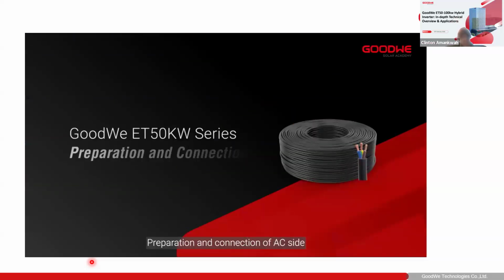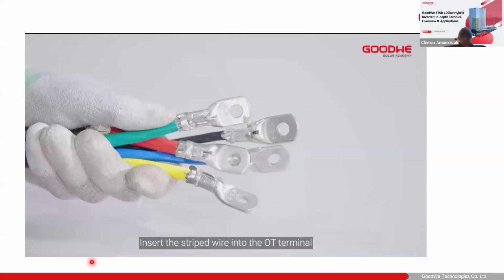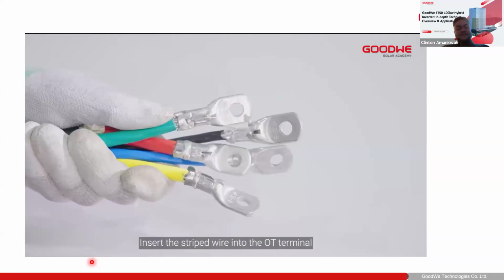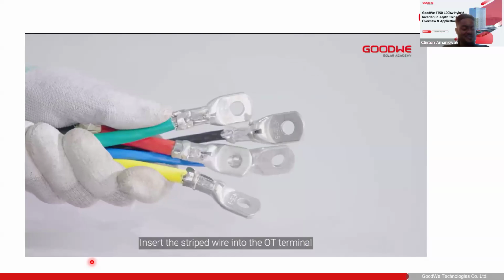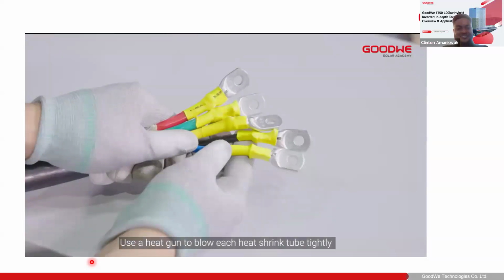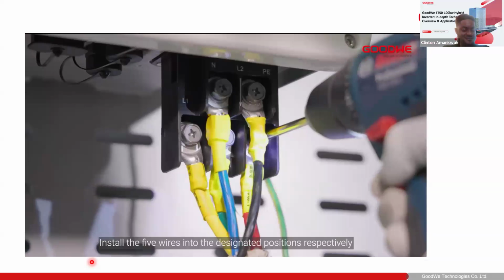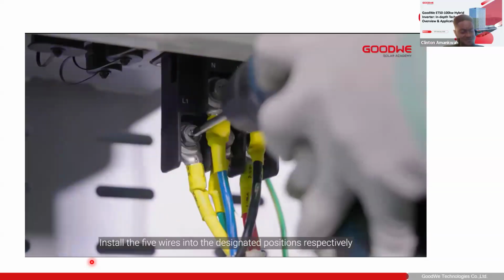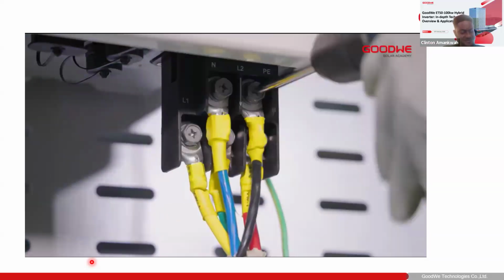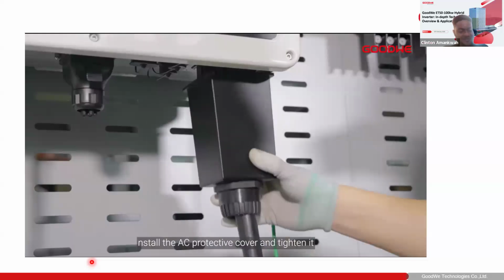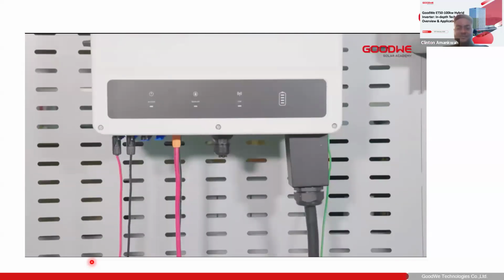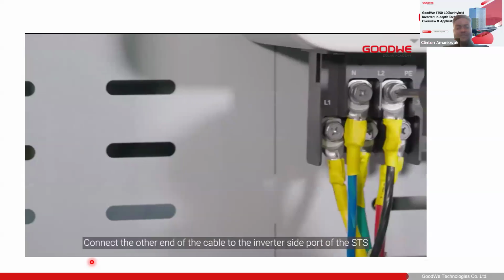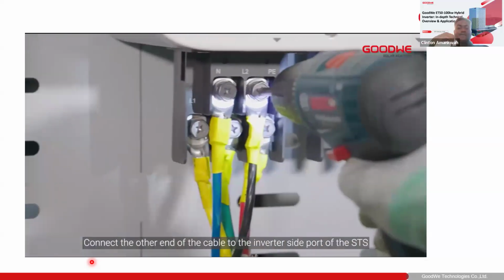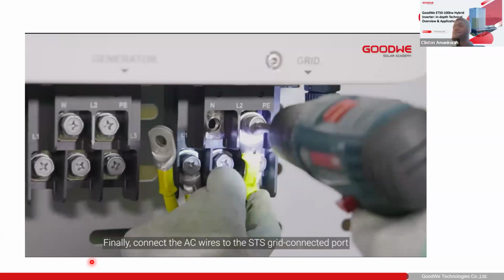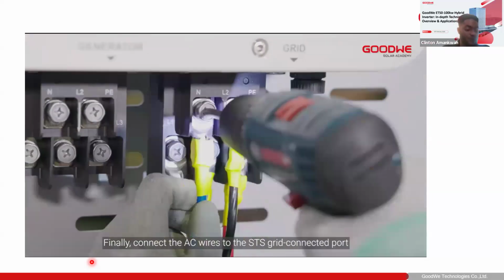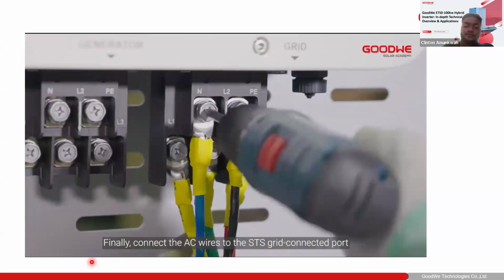Preparation and connection of AC side. Insert the stripped wire into the OT terminal and compress it tightly. Use a heat gun to blow each heat shrink tube tightly. Install the 5 wires into the designated positions respectively. Install the AC protective cover and tighten it. Connect the other end of the cable to the inverter side port of the STS. Finally, connect the AC wires to the STS grid-connected port.